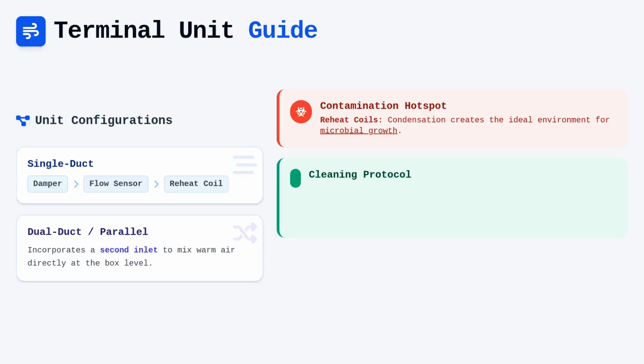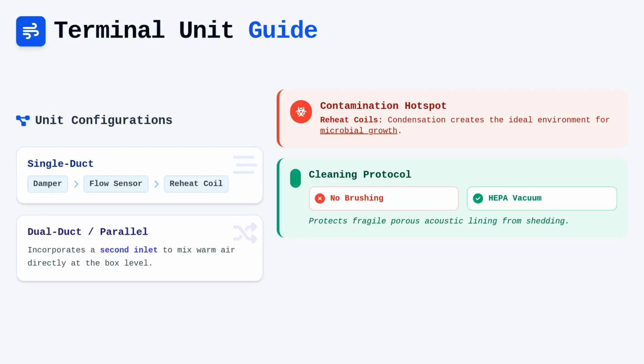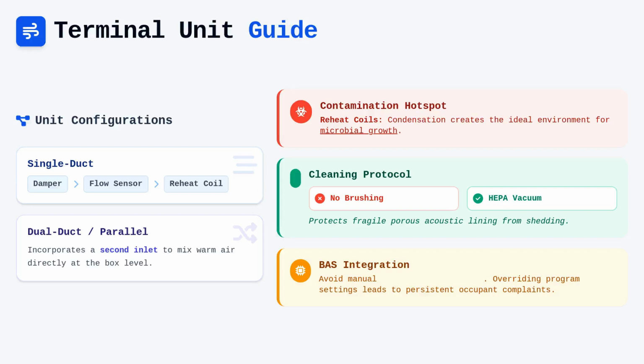You must navigate the acoustic lining found inside many of these boxes, which is porous and susceptible to shedding if scrubbed with excessive force. Cleaning these surfaces requires a methodical approach, often involving high-efficiency particulate air vacuuming rather than physical brushing to prevent the degradation of internal insulation media. Furthermore, you have to be acutely aware of how these boxes interface with the building automation system, as improper manual manipulation of the actuators can override the program settings and create comfort complaints that persist long after you have finished your work.